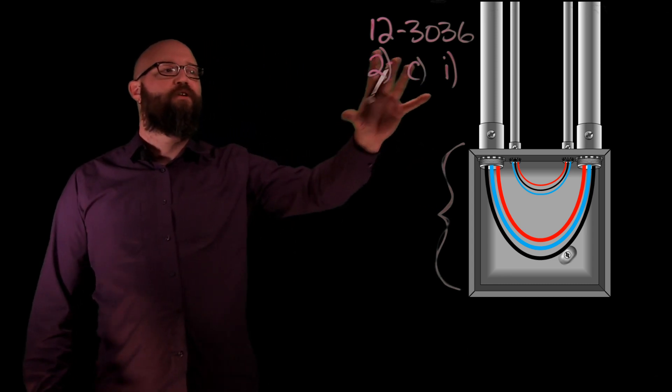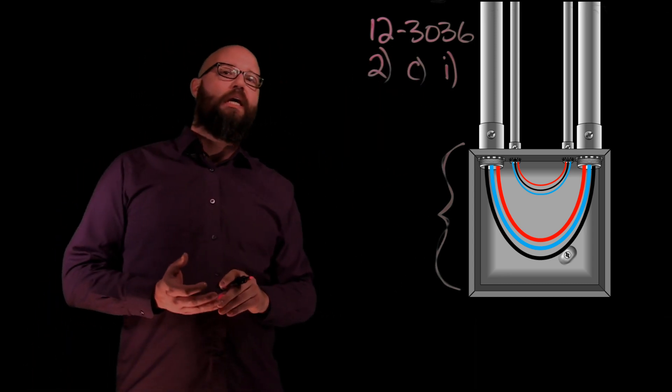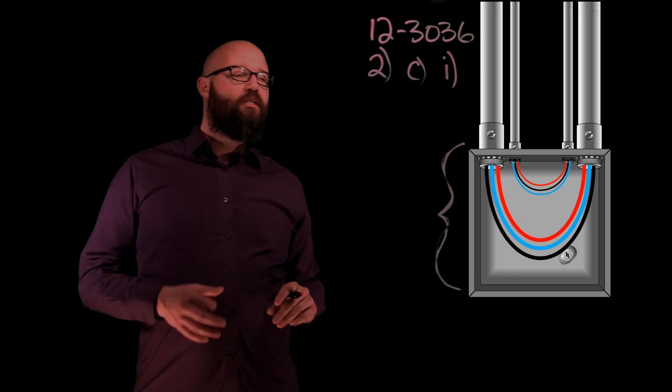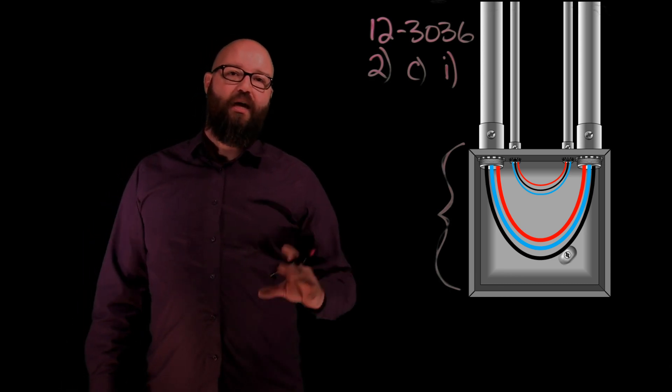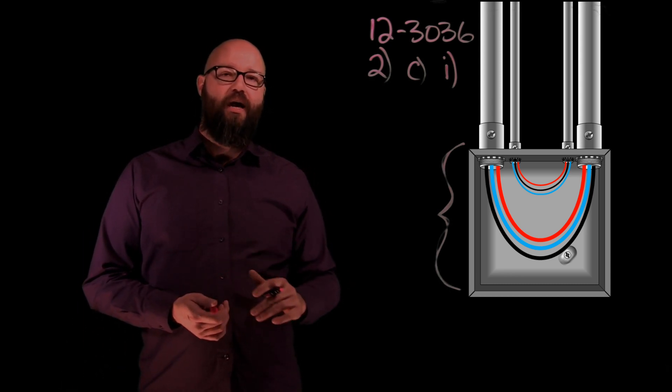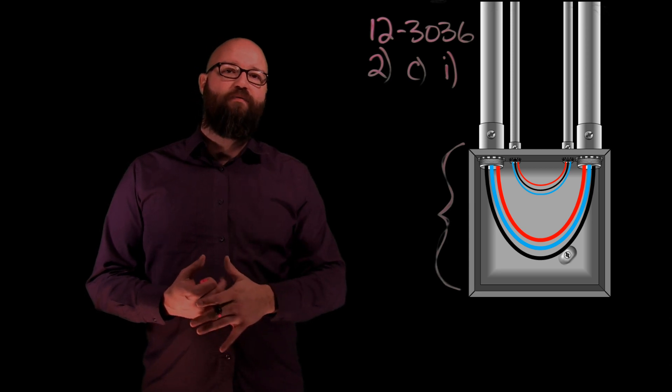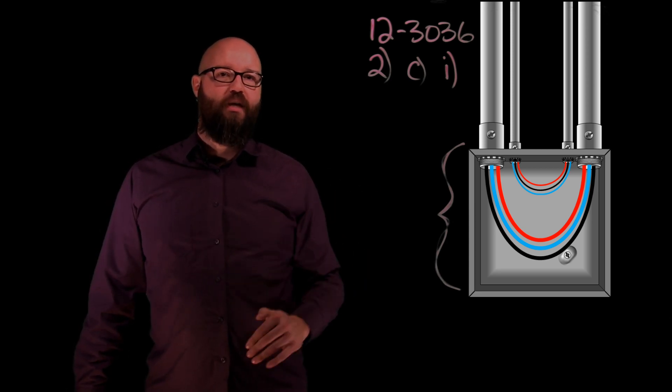So if we take a look at 12-3036 item 2C I, what it tells us is that we're going to take six times the largest trade size diameter and we're going to add the rest of the trade size diameters that are on that same wall.